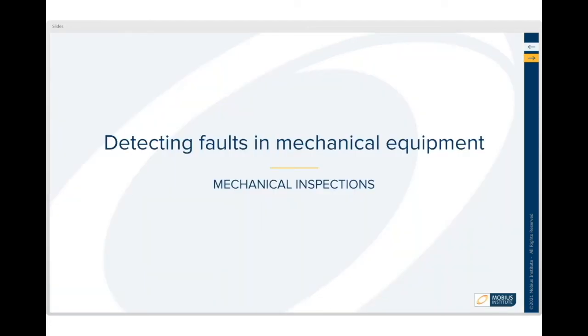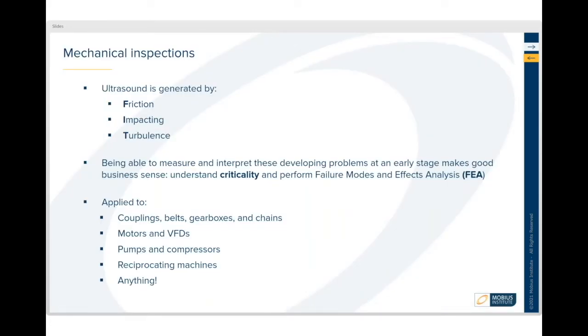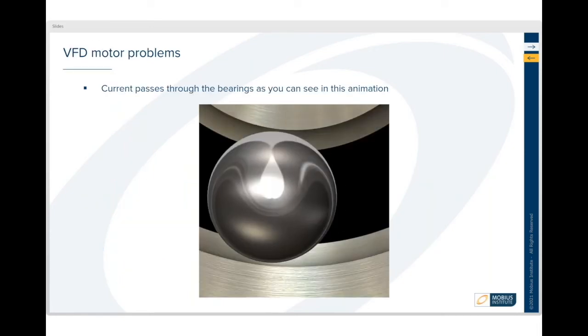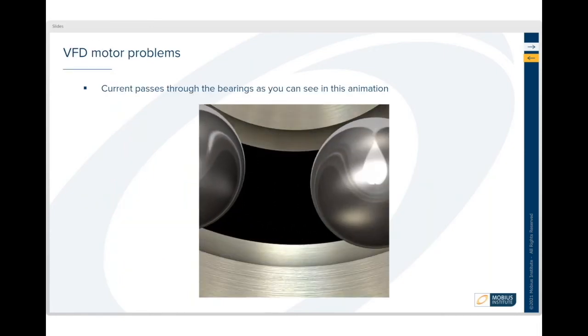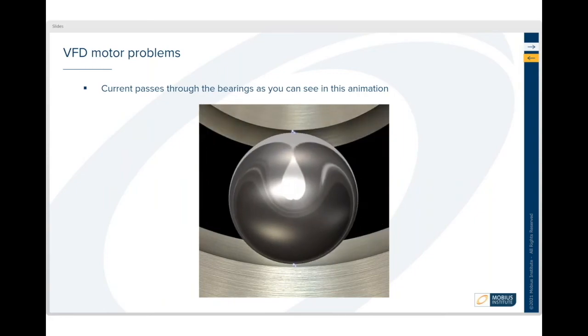There's a lot to learn. We've got all kinds of mechanical inspections we can perform knowing that we can detect friction, impacting, and turbulence. There's a whole range of different fault conditions we can detect. In this case we're looking for arcing. We've got problems with a variable frequency drive. Current passing through the bearing. And you can see the little spark there. And it's causing damage to the bearing.